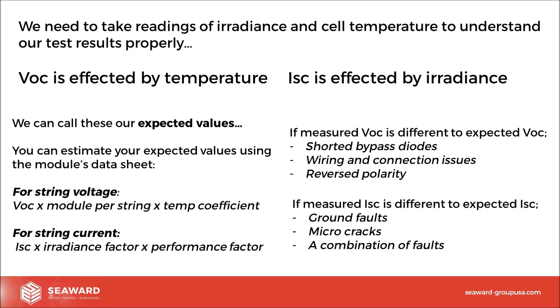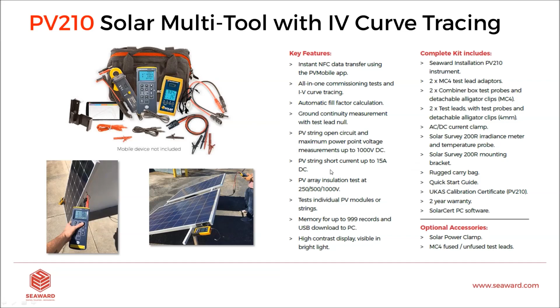So we can do that with a more robust solar PV tool like our PV210. So you can see here that this is going to give you open circuit voltage, short circuit current, insulation resistance, the IV curve. There's also an amp clamp. We're also going to take irradiance, cell temperature, and ambient temperature, and we're going to run through those tests in about 30 seconds. So rather than having to get out your insulation tester, then the voltmeter, then the clamp meter, and doing separate tests and recording them all individually, what this will do is put it all together in one single reporting form for you within about 30 seconds. So we're going to show you some examples of that in the field now.